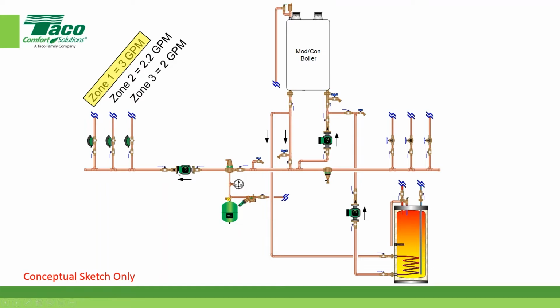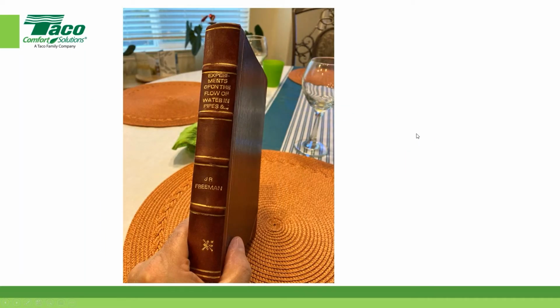And what we're saying here is we're going to measure from the outlet side of the pump, and we're going to start counting things. We got a check valve, we got a ball valve, we got a T on the run, T on the run, T on the branch, ball valve, zone valve, and pipe valves. Everything that's out here, we come back over here. We got a globe valve, we got a ball valve, we got a T on the branch. Come back over here, we got a magnetic dirt separator, T on its back, or on the run, I should say. T on the run as well, ball valve, air separator, okay, back to a ball valve, and now we're at the inlet side of the pump. That's what we're trying to measure when we get that 150 foot, and the equivalency of the valves and everything, okay?